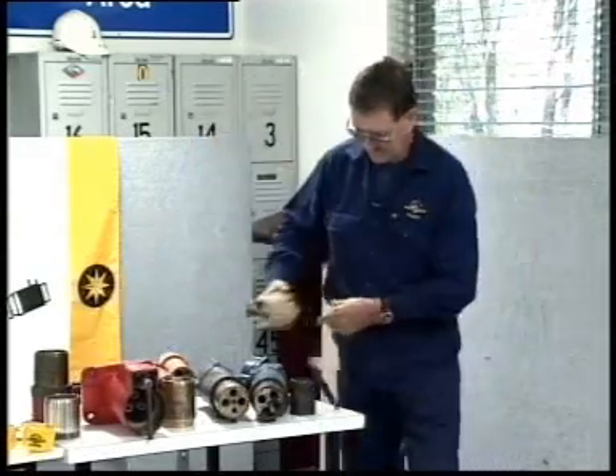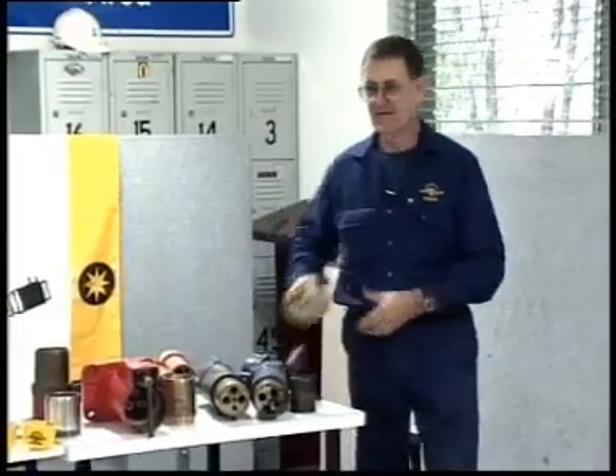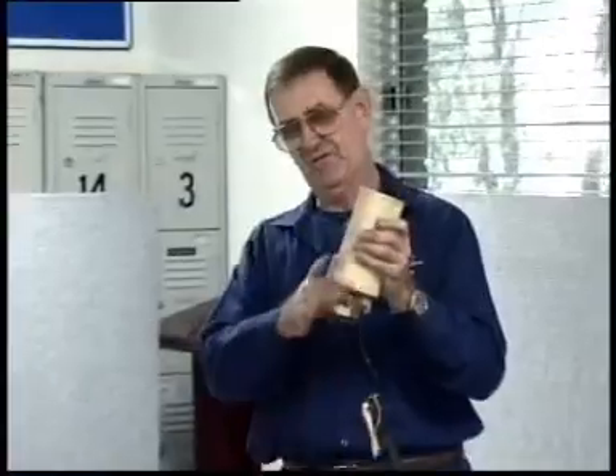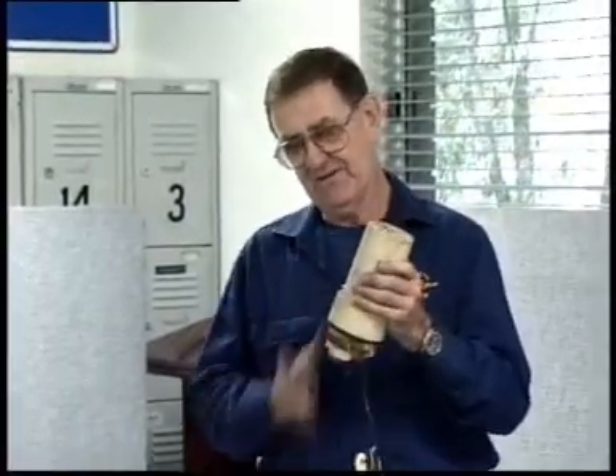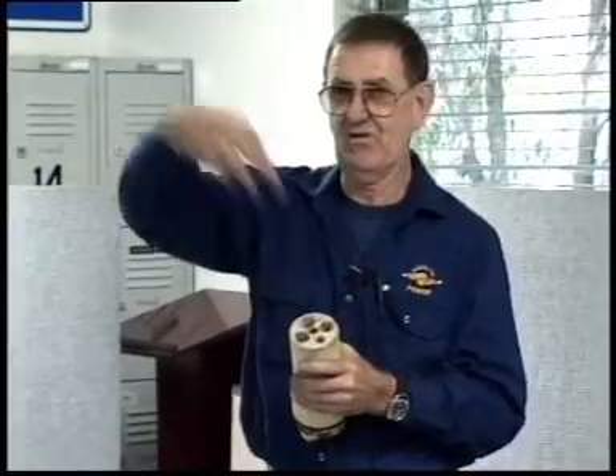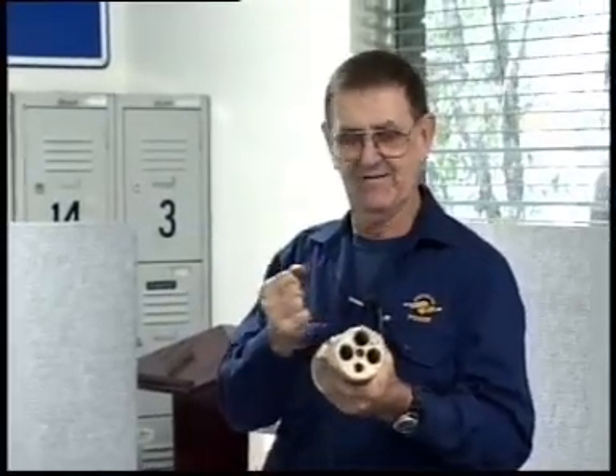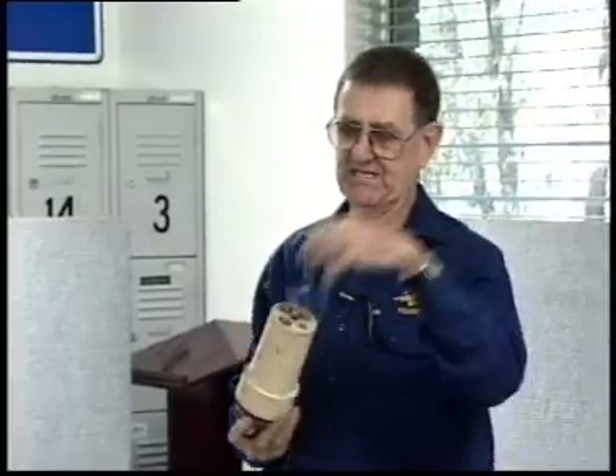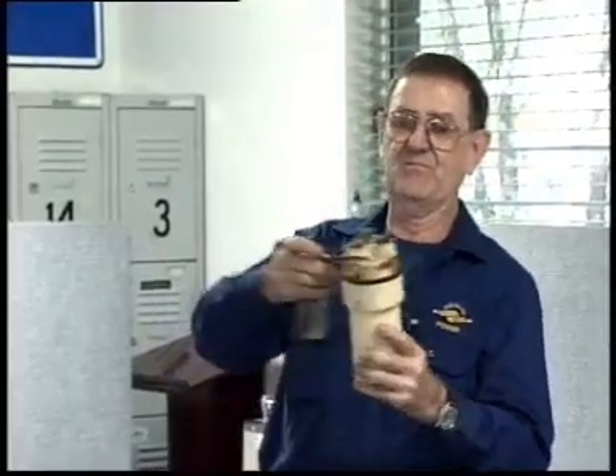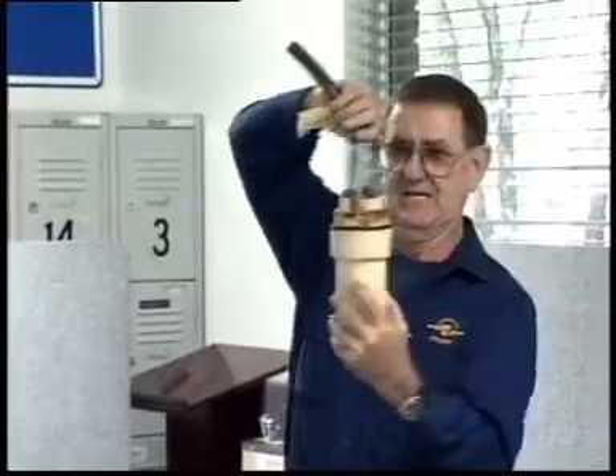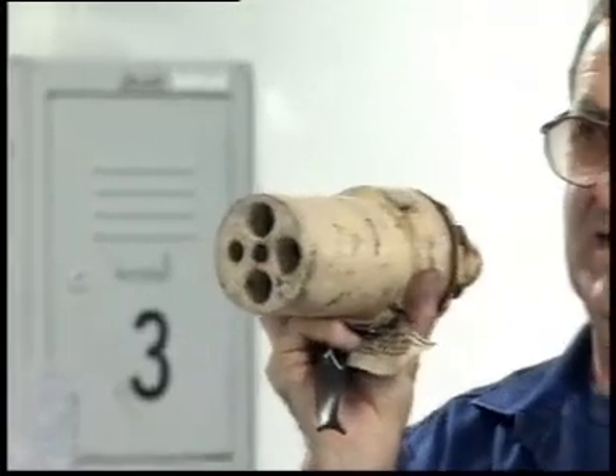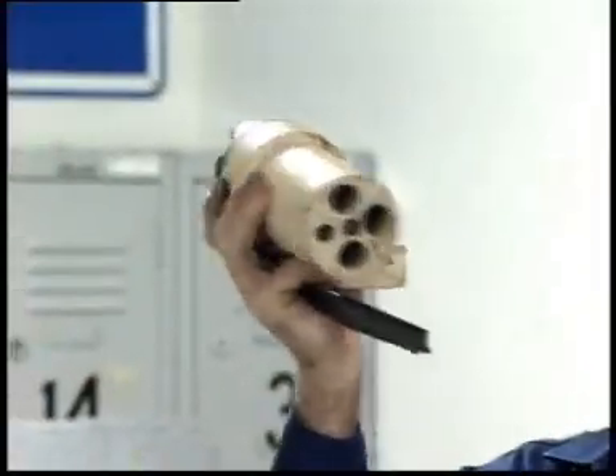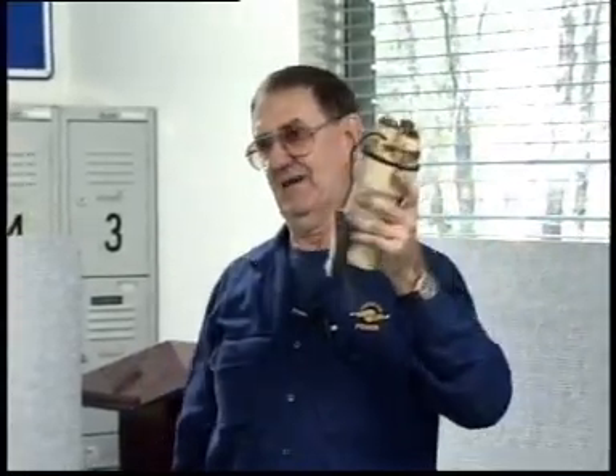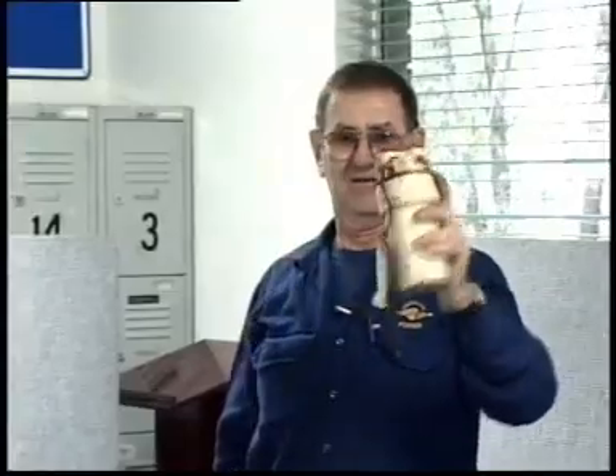Now that interior sits inside the plug there. The cables come in the back end of the plug. They get made off into what we call thimbles, and there's a landing in there where the thimbles sit up against, and then down through the front go the contacts and lock into the thimbles on this landing. So it's held in there fairly firm mechanically. If moisture gets in the front end there, it can go all the way through and get right through the back end, and you can see all the rusted sections in there, in the back end. The front end we can't get apart. It's all rusted in there. All of the contacts are rusted and all the screws holding them. We have to throw that away, which we had to do with this. There's about $300 worth of equipment there alone, without having to spend a couple of hours to remake it off again. A lot of money involved.